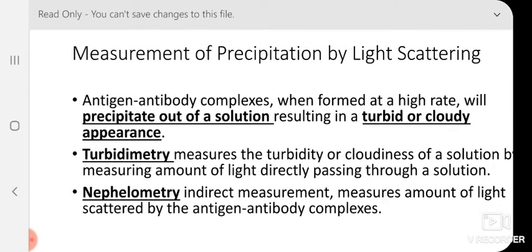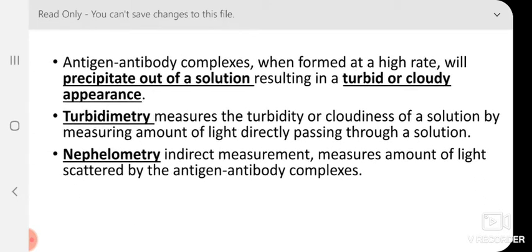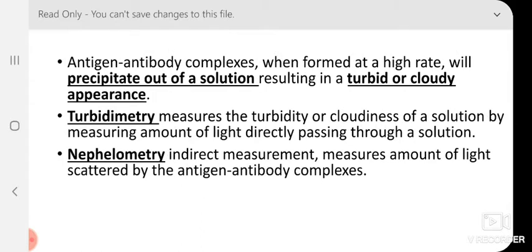There are many methods whereby we can measure the precipitation. One such method is light scattering. Antigen-antibody complexes, when formed at a high rate, will precipitate out of solution, resulting in a turbid or cloudy appearance. One branch of science called turbidimetry measures the turbidity by measuring the amount of light directly passing through a solution. Another branch called nephelometry directly measures the amount of light scattered by the antigen-antibody complex. By measuring these, we can quantify how much precipitation reaction has taken place.